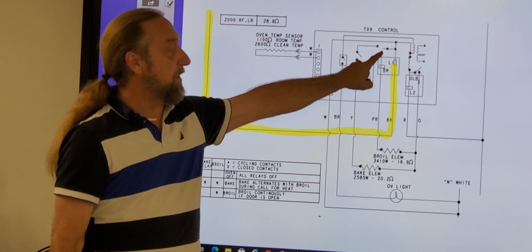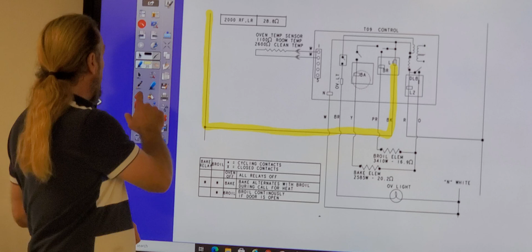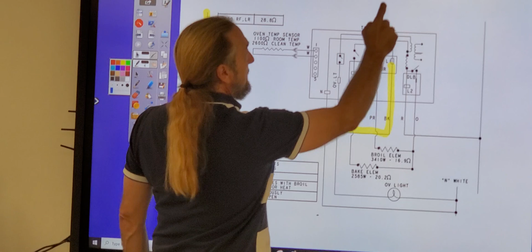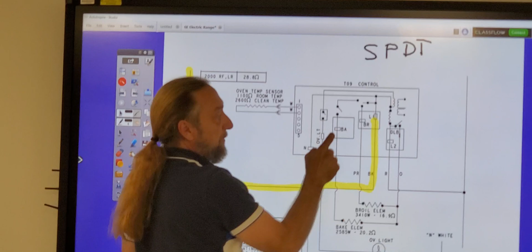Notice the Broil Relay. What type of contact is that right there on the relay? That's a normally open contact? Nope. That is a single pole, double throw. That's a single pole, single throw. So the bake relay has only got a single switch. The broil relay can go down here or up here. It can go down or up. It has two different positions on the relay. Okay? We'll go through those circuits in a minute as we explain each diagram.